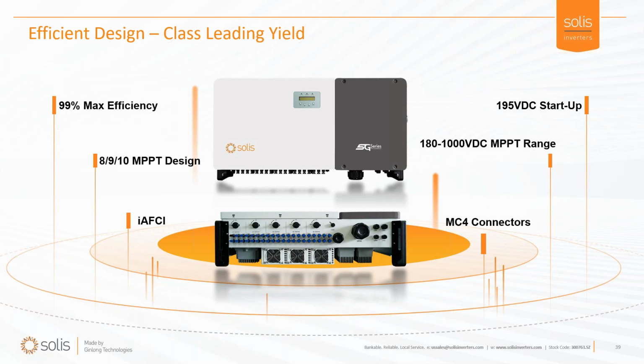Now take a look at those segmented DC connectors there—you can see the big AC connection base, our communication ports, and the inputs. Look at all the inputs, 20 inputs, but all of those inputs can handle the full load of the MPPT, which means that even though you've got 20 inputs for 20 strings, you could Y connect in the field and only bring 10 strings back, really reducing your cost. It's broken up into 5 essentially separate inverters, so when that intelligent arc fault sends an alarm, it's going to tell you which MPPT it's on. You can go out there, isolate, lock out, tag out that DC disconnect switch, and turn everything else back on.